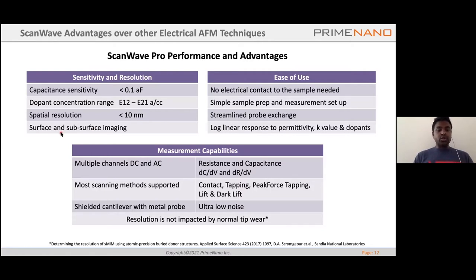As we are using microwaves, you're not only looking at the surface information or the surface response, but you can also look at the subsurface imaging as well. The unique advantage of microwave is that you do not need any electrical back contact to the sample. This minimizes the sample preparation in the sense that you can also look at devices which are on insulating substrates or glass, quartz or sapphire, or silicon on insulator kind of devices can also be easily imaged. We have made sure that these probes are very similar to the commercial probes. It makes the user experience much simpler and the learning curve much easier. The other USP of the microwaves and the ScanWave systems is the response to variation in the permittivity. I'll talk about this in detail in the next slide.